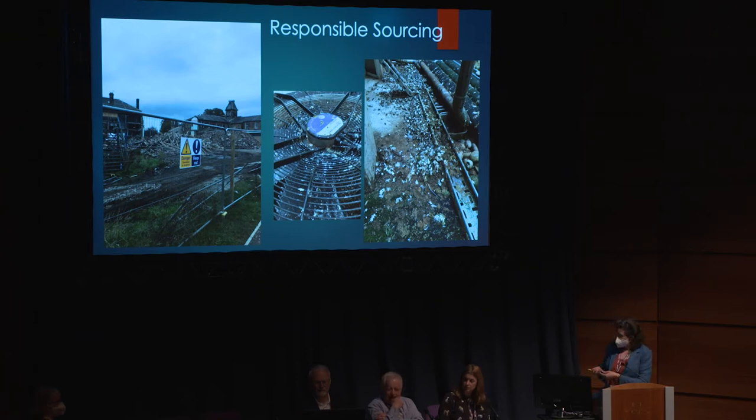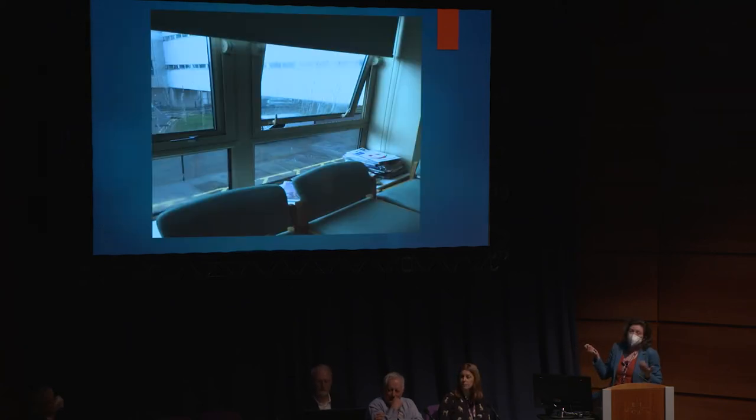Here's an outside area with lots of pigeon guano and a fan designed to cool off a piece of machinery. When switched on, hot air rises and the fan pushes it up - no big deal, unless straight above it is an air inlet. So you've got all sorts of pathogen potential going up. Thinking about natural ventilation - we've been going around telling everybody to open their windows - except if this is a staff room in a theater suite with bird droppings present, and the air is blowing in with the doors open.